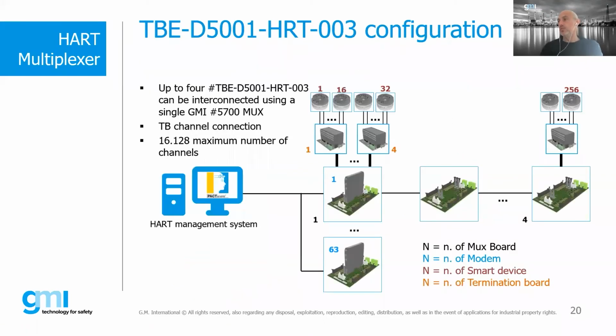Okay, and this is how to use it. Here you have the solution with the transmitters, in this case an example of 256 channels. Those transmitters are connected to the isolators in the termination boards that we saw previously, and the termination boards are connected to the HART multiplexer. What we want to highlight here is that there is one HART multiplexer for 256 channels. You need other termination boards to connect the other isolators or termination boards, because that is mechanically necessary, but the multiplexer is just one.